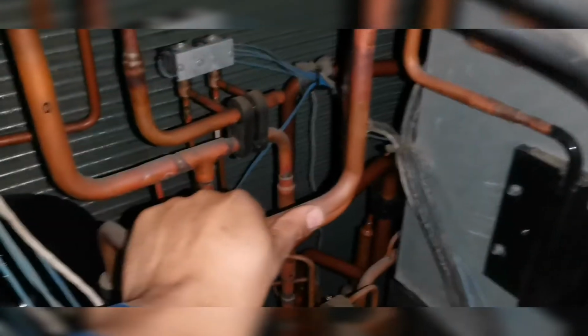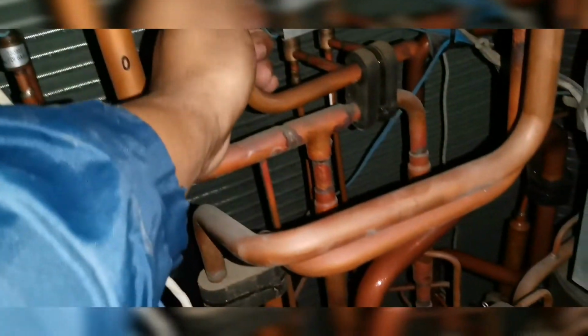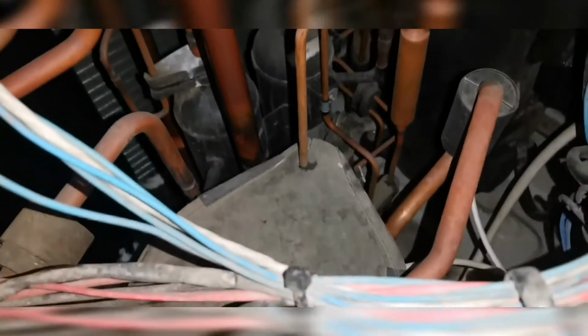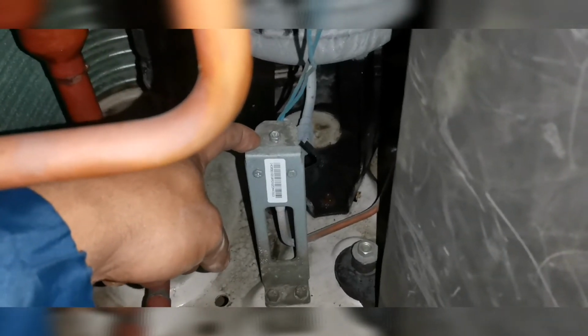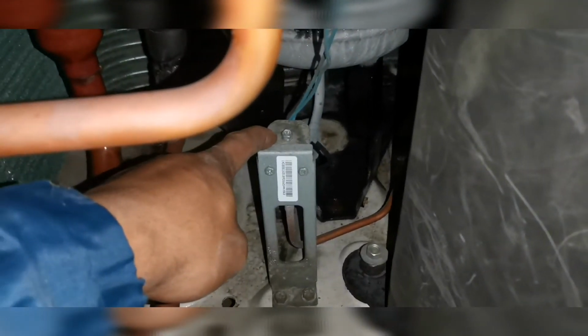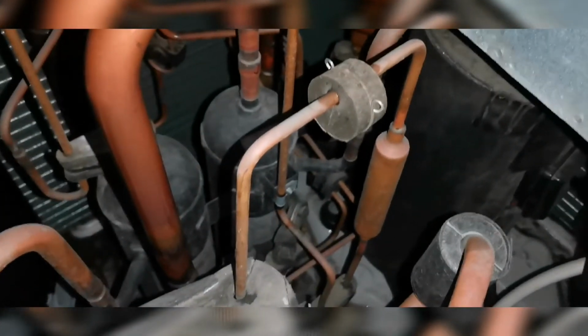So yeah, that's a cool vapor line. Same with the EVI, your vapor injection into the compressor, just to manage air temperature. So once we're happy with everything, what is very important is that we check this valve right here for proper function. This is our accumulator return valve, which returns oil back to the suction side, returning it back to the compressors.